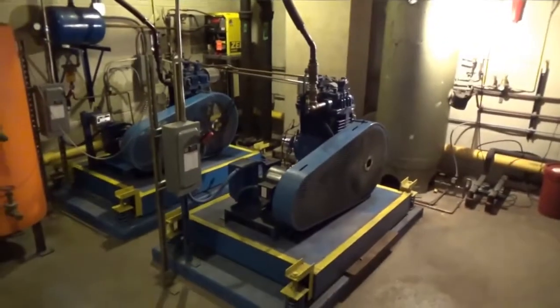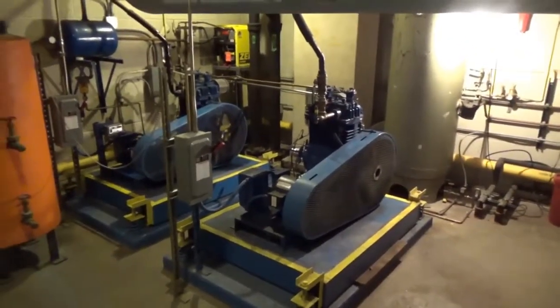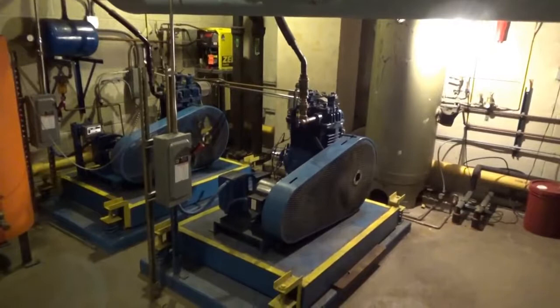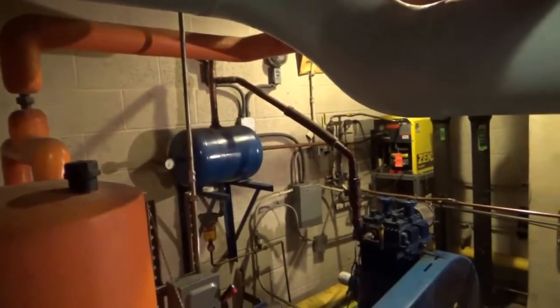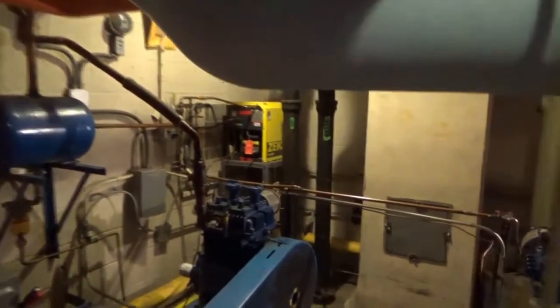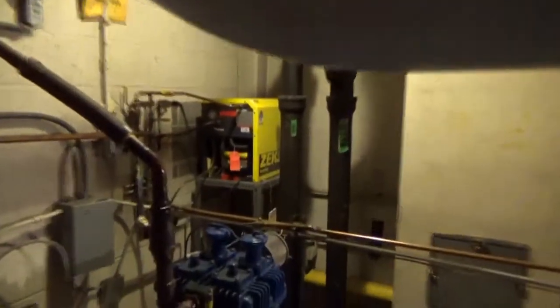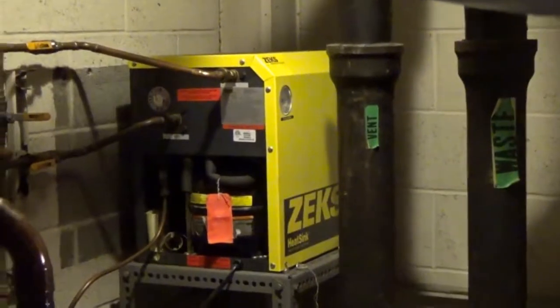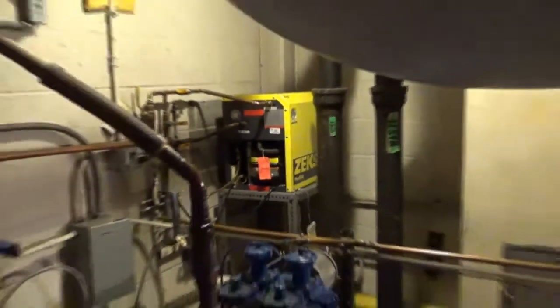This is our air station, and what the air station does here in the hotel is it controls all the pneumatic valving for the heating and cooling system. It's two big Quincy compressors. And then in the back corner you can see we have an air dryer, and the air dryer simply removes moisture so that we're not getting any water into the pneumatic valves.